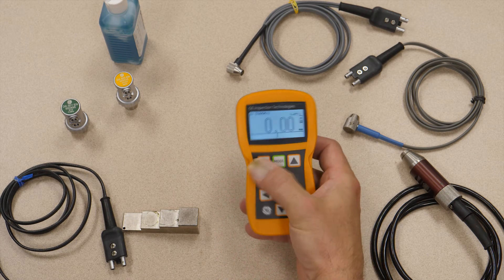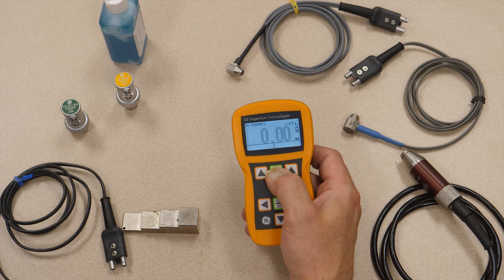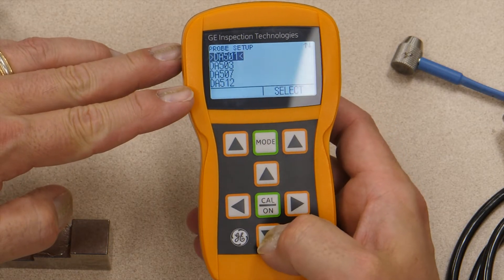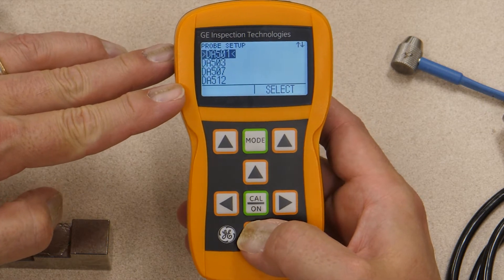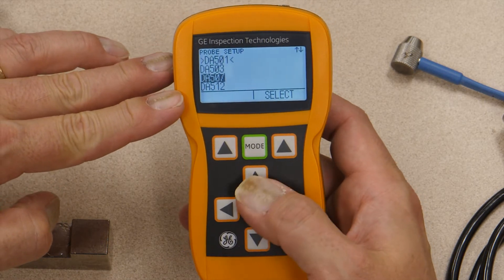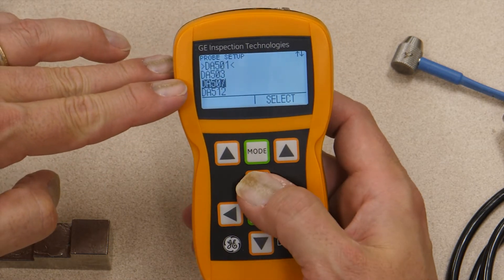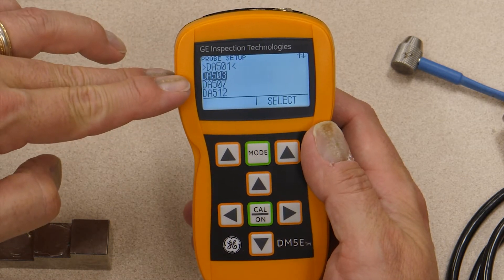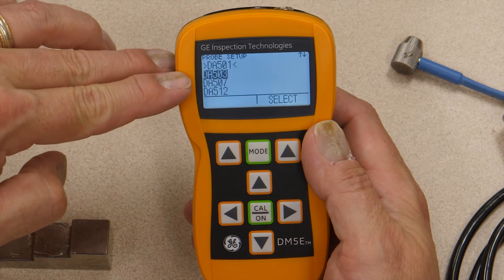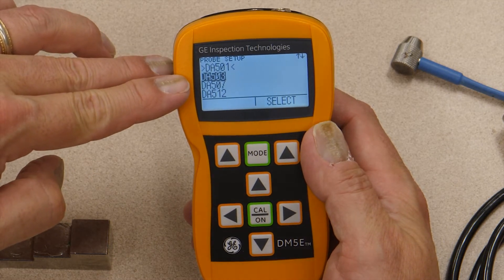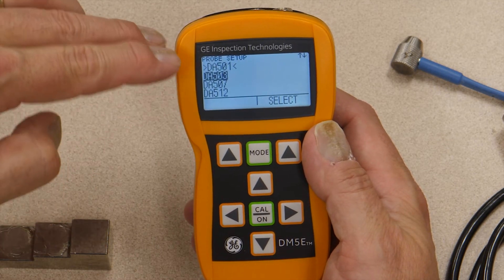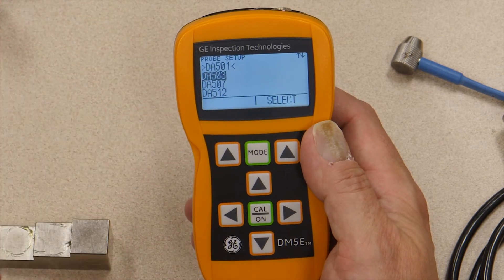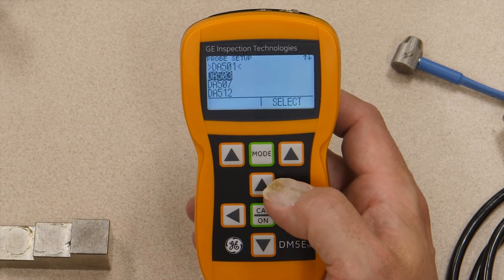To do that, you have the instrument running, press the mode button, and it brings up the list of supported probes. You can scroll up and down. You notice there's a black cursor. As I use the up and down keys, I can move through the list and the black cursor follows. The black cursor is not telling me which probe is currently selected though. The selection of the probe is indicated by the greater than, less than brackets on either side of the selected probe.